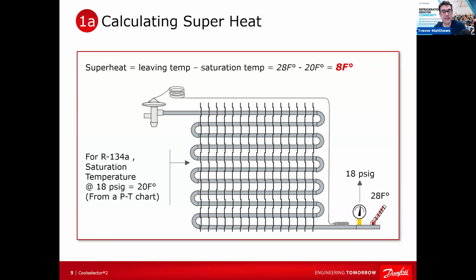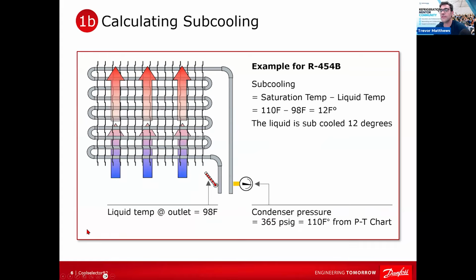And the big thing is that you got to do all your checks first. And we'll get into the troubleshooting too. You got to make sure that coil's clean, the fans are running, the filter's not blocked. There's so many different things that we need to check before we just start. And we can walk you through and tell you the difference. Yeah, it's so important. Well, let's dive into subcooling now. So subcooling is another important thing. Yeah, probably even more so nowadays with adaptive controls. So subcooling in a condenser is a little bit different because basically going into your evaporator, you're at what's called saturation. So you go through your metering device and it expands.